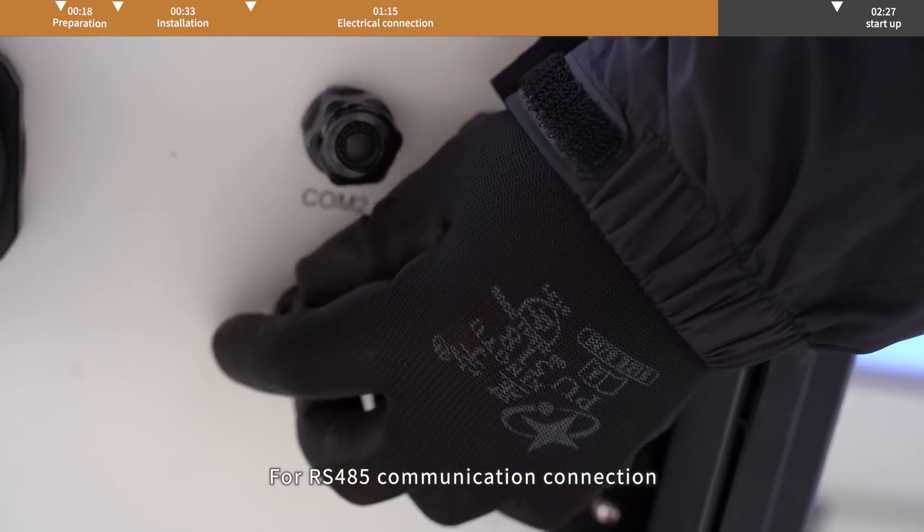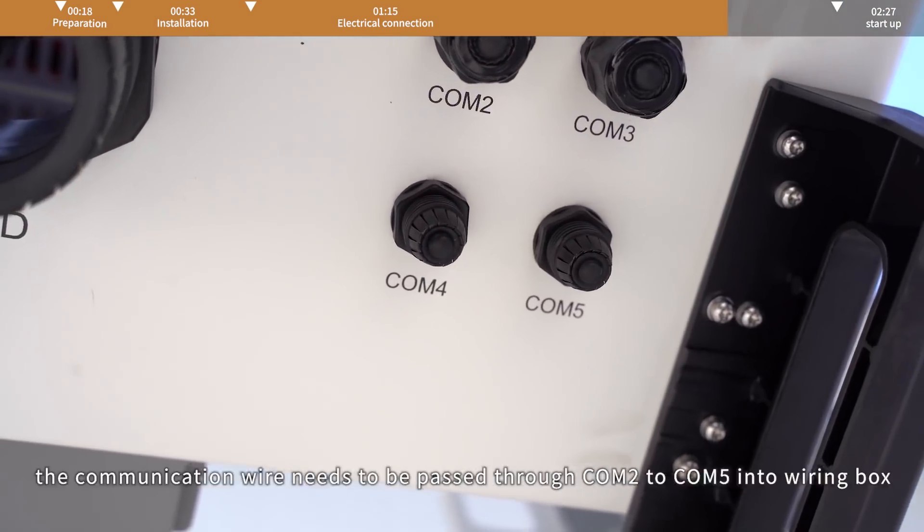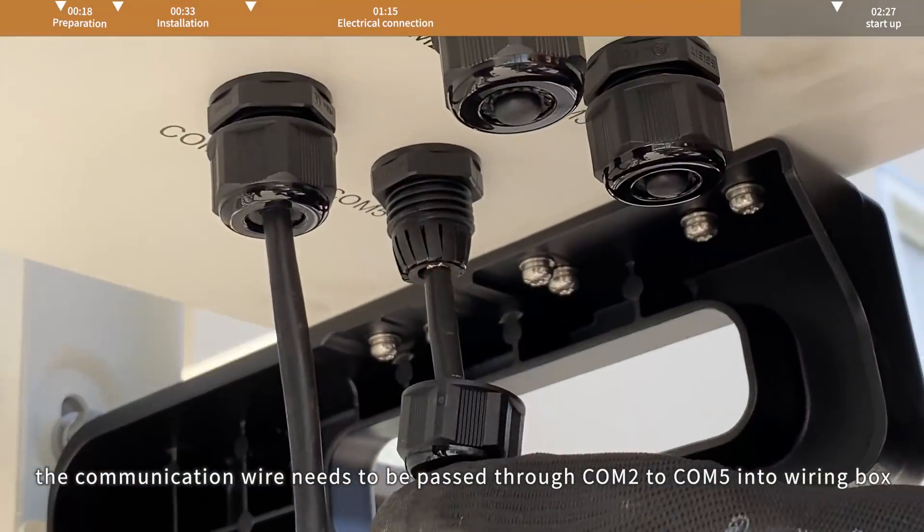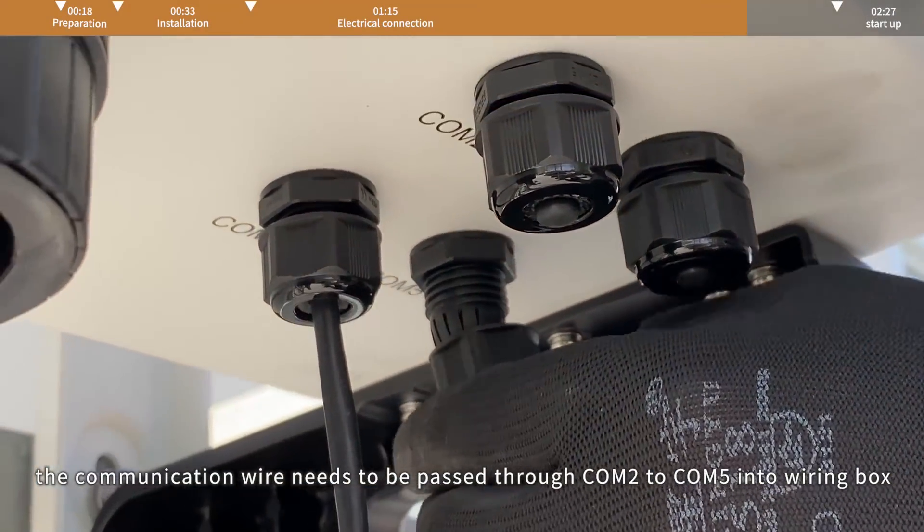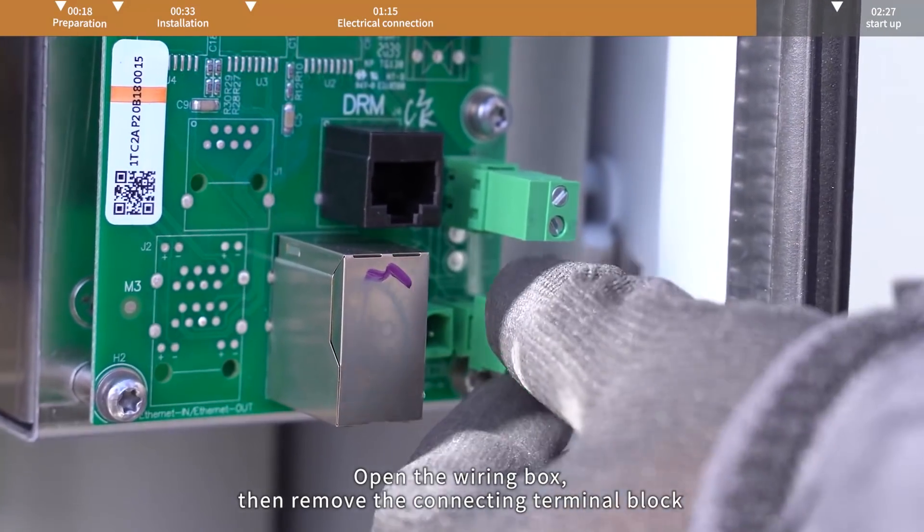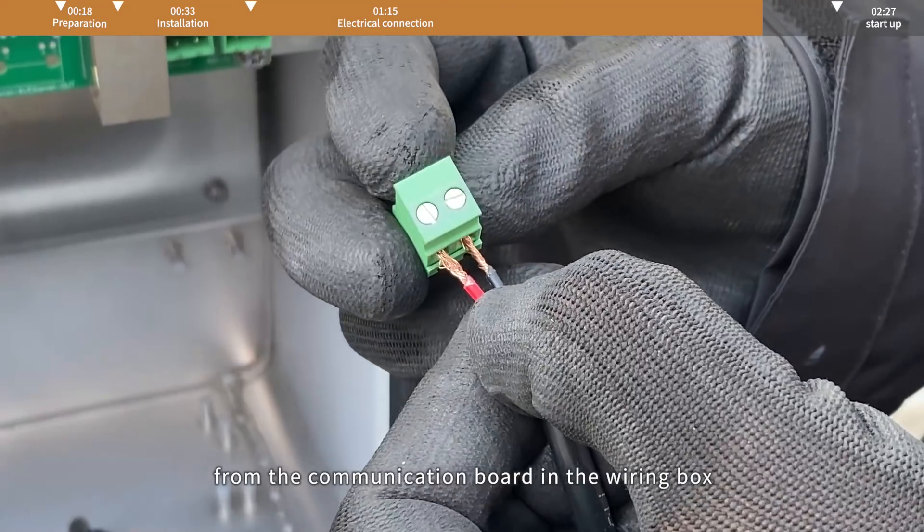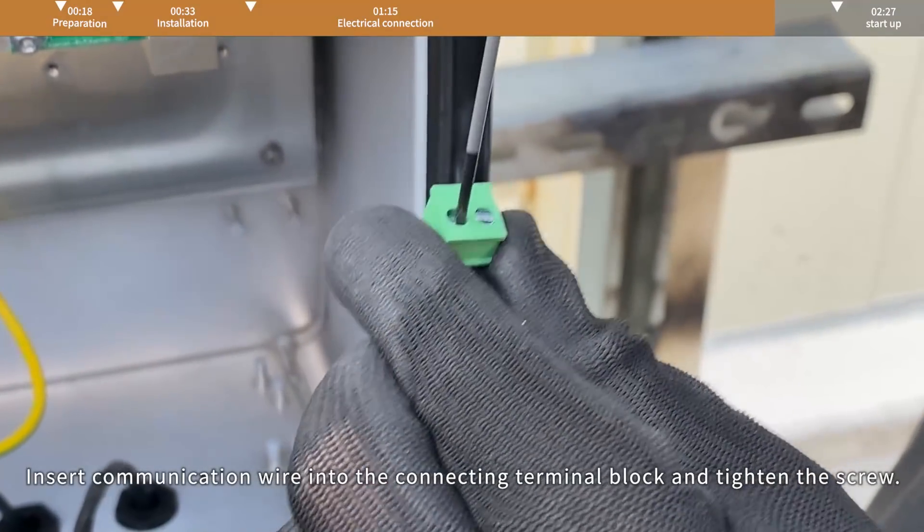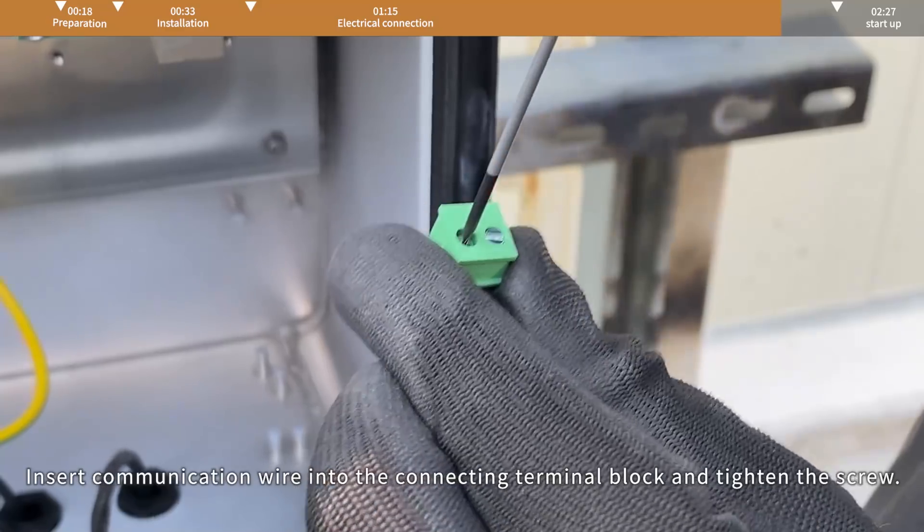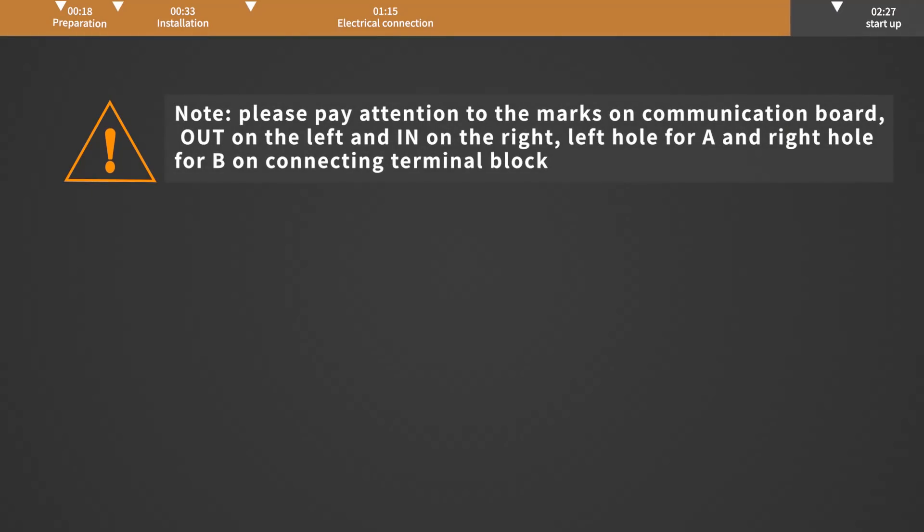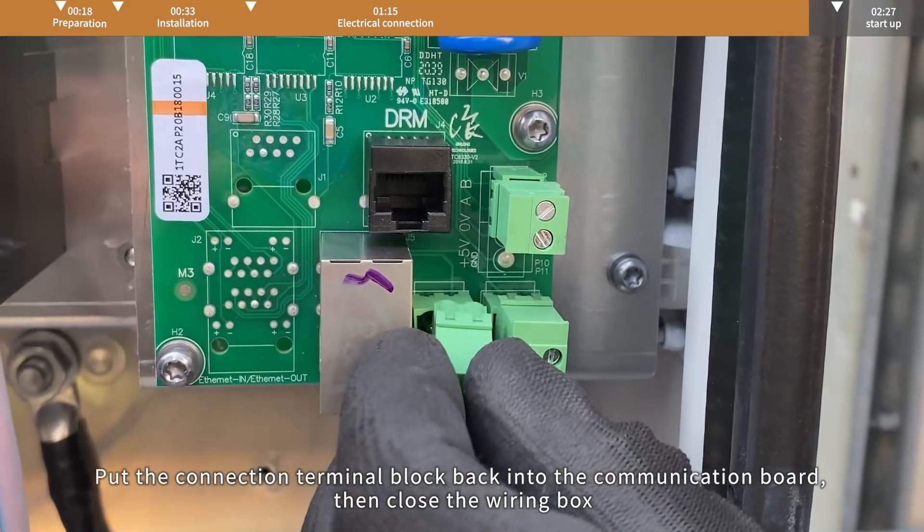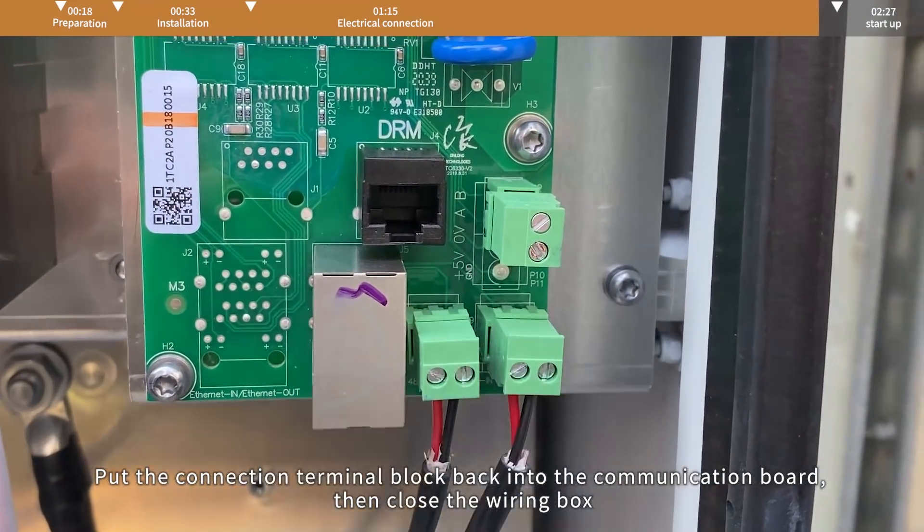For RS-485 communication connection, the communication wire needs to be passed through COM2 to COM5 into the wiring box. Open the wiring box, then remove the connecting terminal block from the communication board. Insert communication wire into the connecting terminal block and tighten the screw. Put the connection terminal block back into the communication board, then close the wiring box.